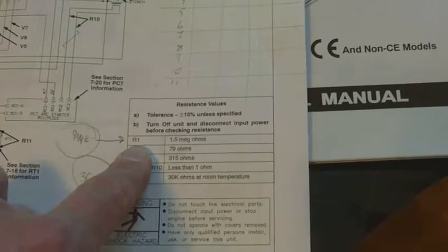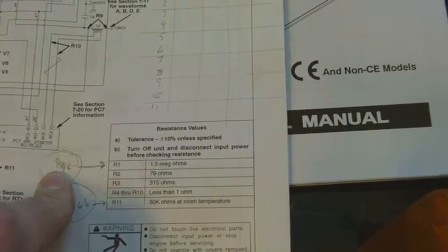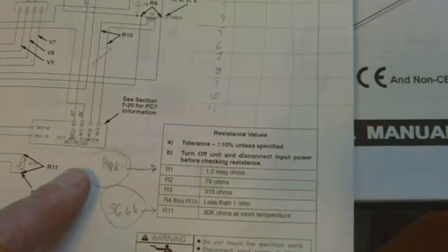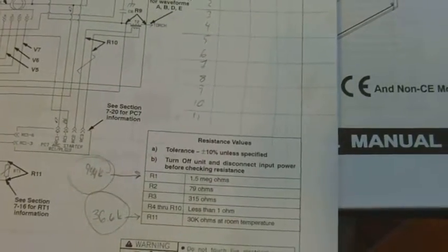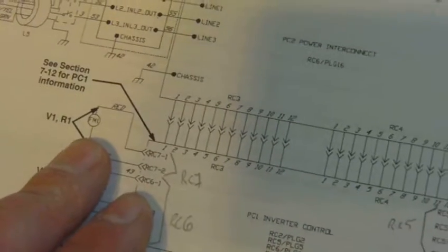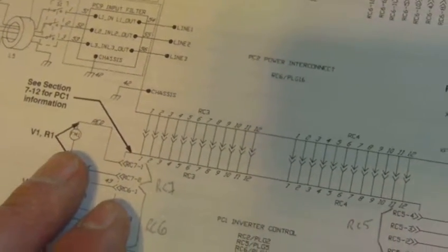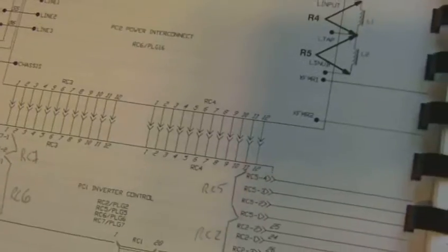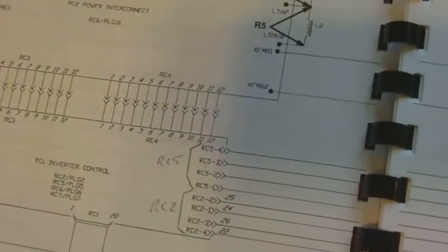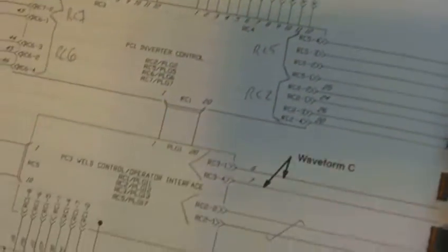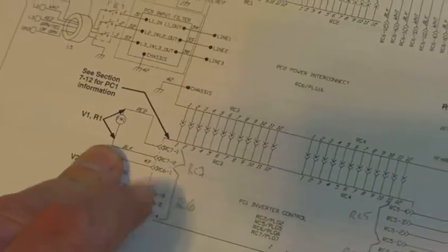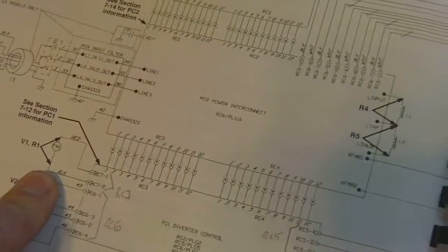Now R1 came in at 944 kilo ohm, should be 1.5 mega ohm. Thing is, that is actually, where is it? Over here. That's the fan motor. So the fan is seeing more resistance than it should, but the fan only comes on when the machine's in need of cooling, so chances of that keeping the machine from turning on at all are very slim. So I moved on.